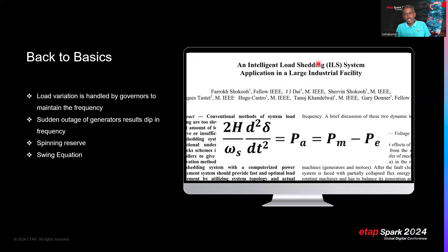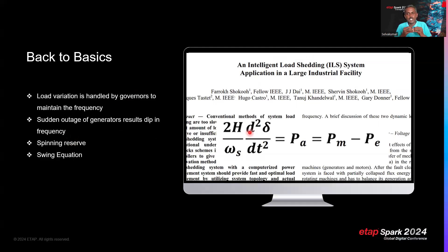A recommended reference is the IEEE paper 'An Intelligent Load Shedding System Application in a Large Industrial Facility,' published by ETAP around 2008, which discusses how to perform intelligent load shedding when an industrial facility disconnects from the grid. In our case, the focus is on how to optimally size the battery energy storage system to maintain spinning reserve and prevent load shedding. Load variation is handled by governors; sudden generator outage causes a frequency dip; spinning reserve must be maintained for both load and wind variation.